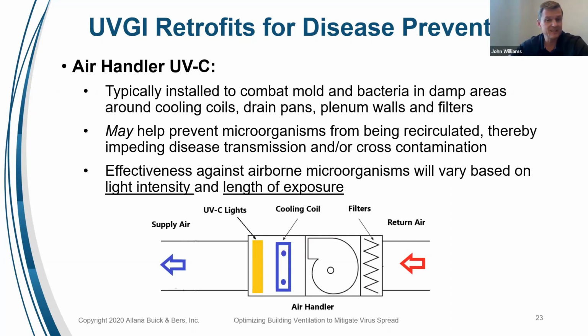The air velocity typically is going to be too high for those microorganisms to be killed simply by passing through that light for a very brief period of time. The way I like to explain it is I don't get a sunburn when I walk from my house to my car. I'm not exposed long enough. The intensity and the length of exposure is not enough for me to be sunburned. Just like the air passing through a UVC light, there's not enough intensity or exposure to necessarily kill what's carried airborne in the airstream.